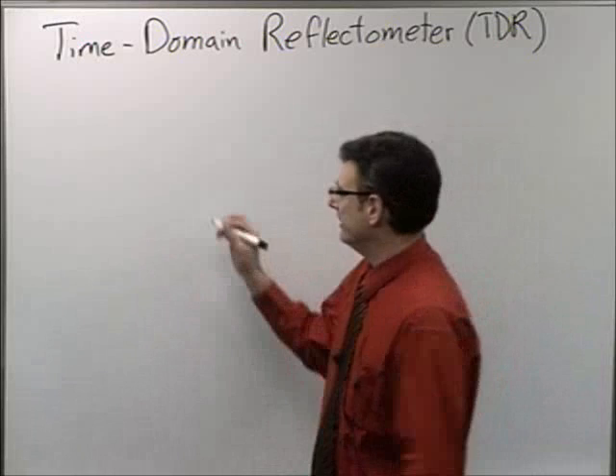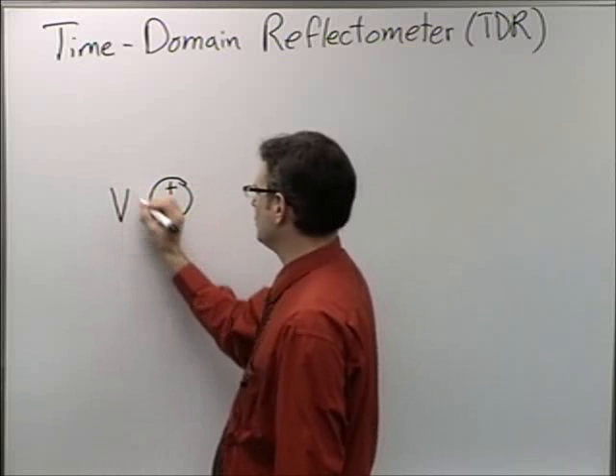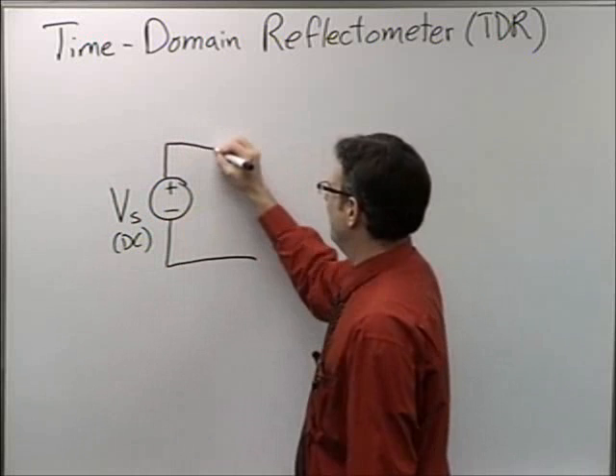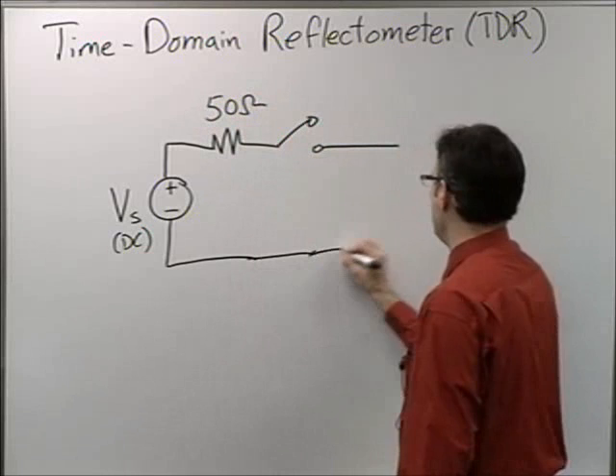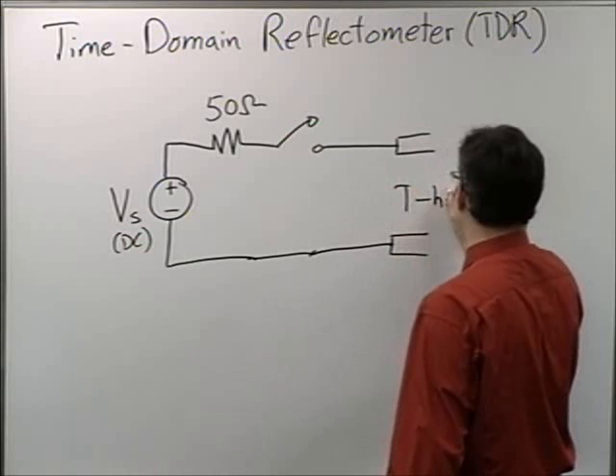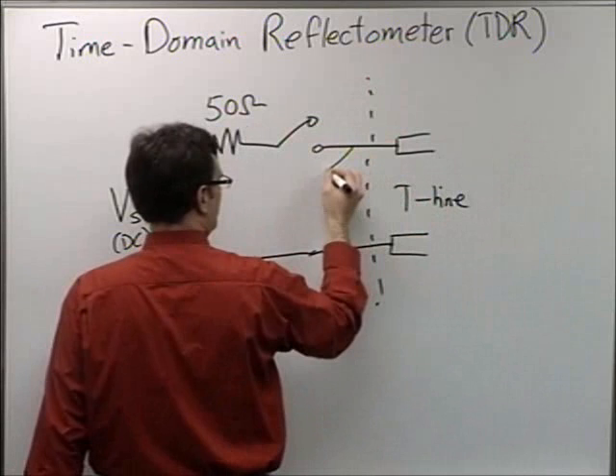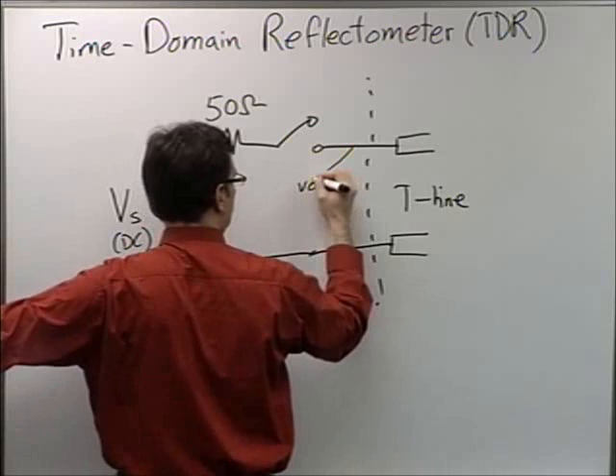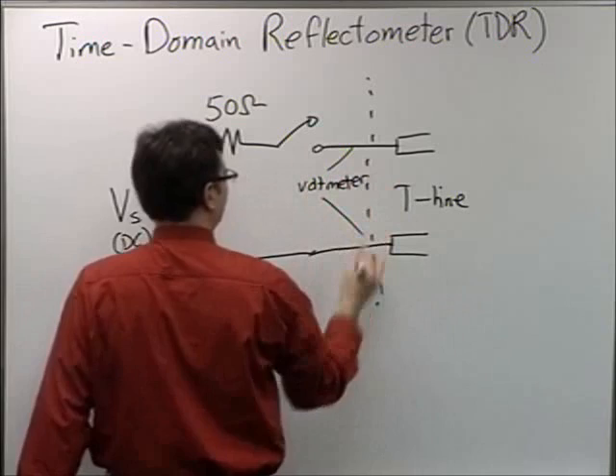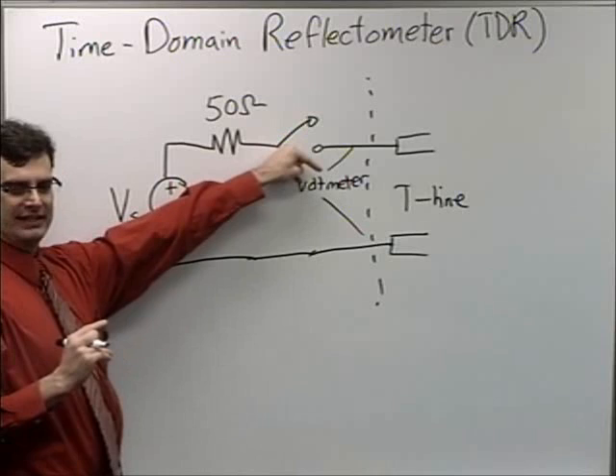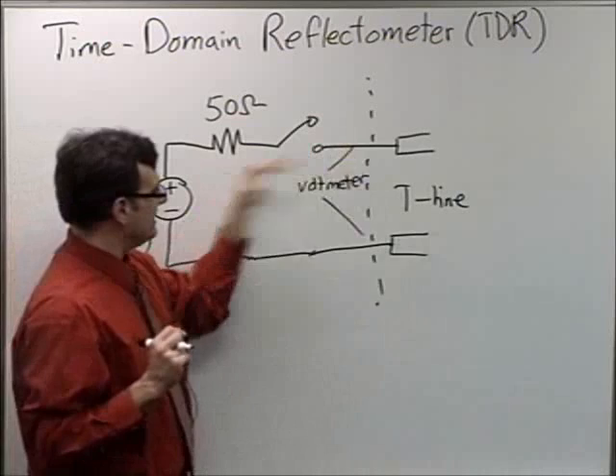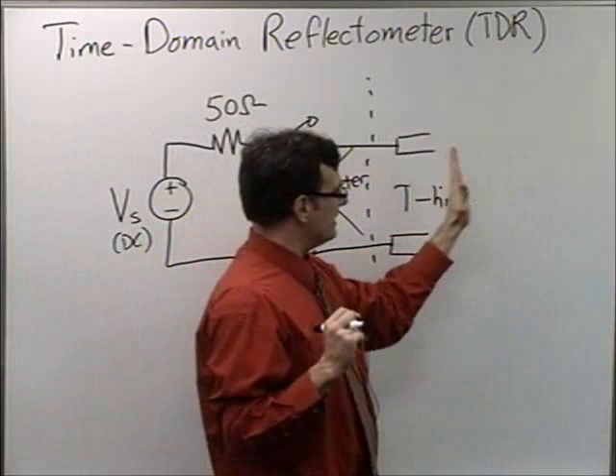The TDR has a very well-calibrated DC voltage source, a carefully matched 50-ohm impedance, a switch, and a very precise voltmeter — which is effectively what you see on the output screen. It clicks down a nice sharp transient, so you get a perfect DC switch source. You can see the magnitude as the source propagates down the line, then some time later it reaches the end, there may or may not be a reflection, and you register the reflection as well as the total voltage.